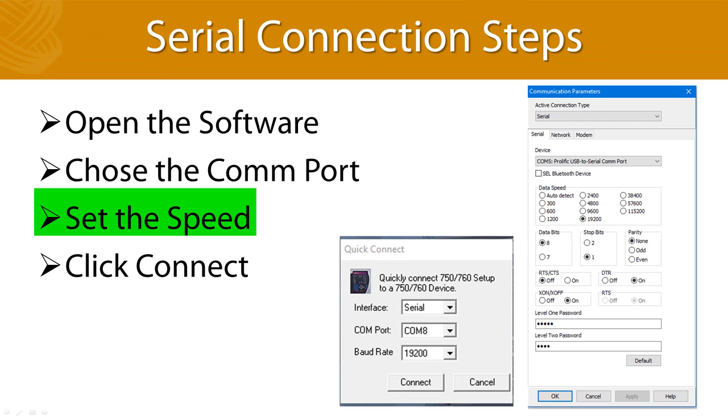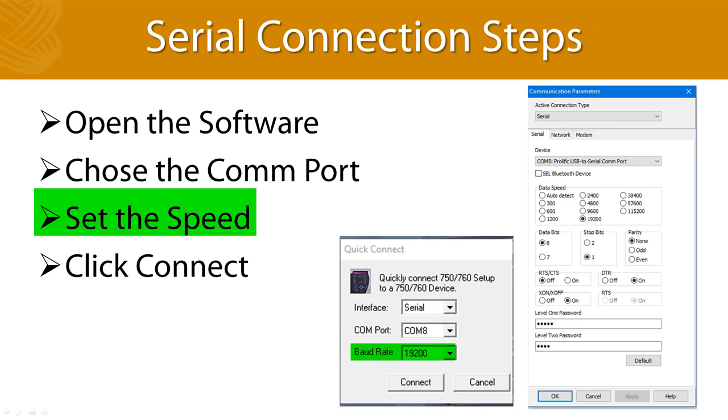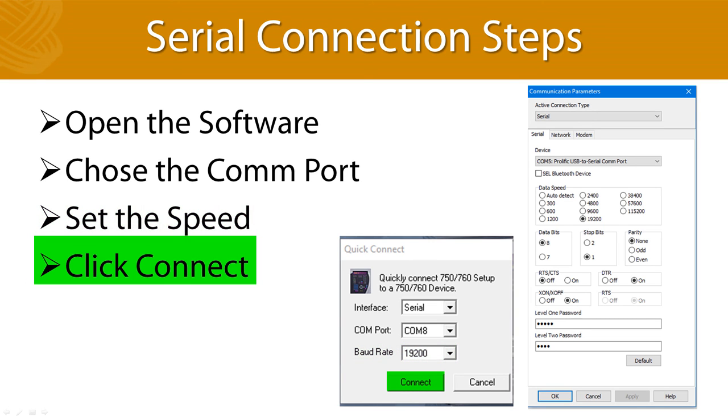I like to find out what the final baud rate will be from the settings, and then set the port speed to that before I start communicating so that I don't have to worry about losing communication when I send the settings in bulk. You shouldn't set the baud rate higher than 38400 because serial communications can get flaky when speeds get higher. Most people have settled on 19200 baud as a good trade-off between speed and reliability. Once you get the baud rate set, you want to click Connect.